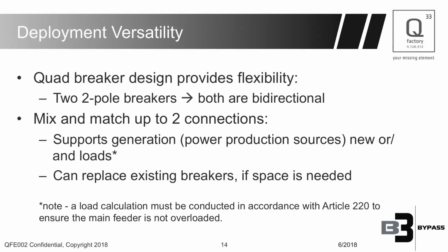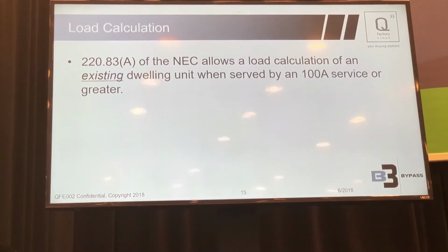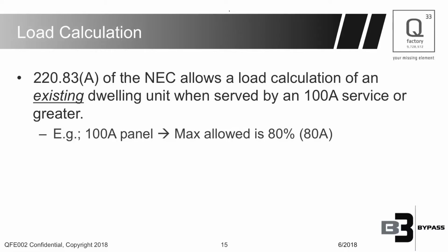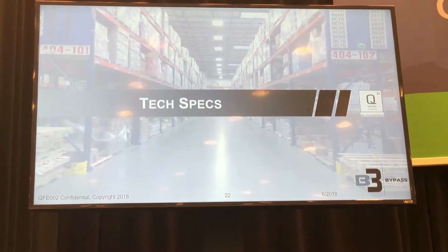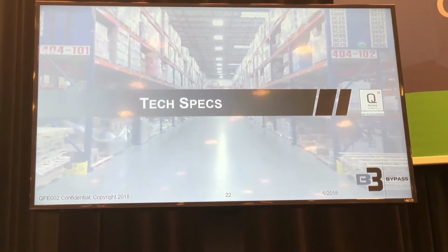Additionally, if there's not space in that main panel and you need to pull an existing breaker, you could pull that and land that load on one of the 2 poles, assuming that the feeder wires are rated to handle that load. If you're adding a new load to the B3, it's allowed, and NEC section 220.83(A) says you're allowed to add new loads to the line side, but you need to do a load calculation. So any questions on that? We can help you out offline if you need to do a load calc.